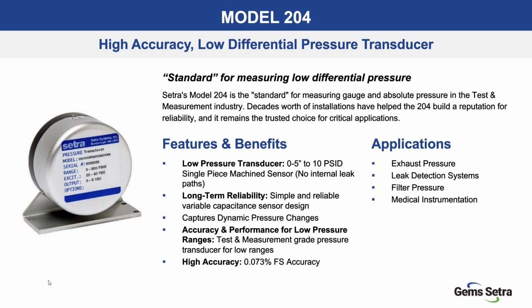Now following up with our model 204, high accuracy, low differential pressure transducer, the standard for measuring differential pressure. Able to measure gauge and absolute pressures as low as 0 to 5 inches to 10 psi differential. Again, it's a single piece machined sensor with no internal O-rings, and exceptional long-term stability. Accuracies as high as 0.073% full scale. Typical applications this product serves include exhaust pressures, leak detection systems, filter pressures, and medical instrumentation.